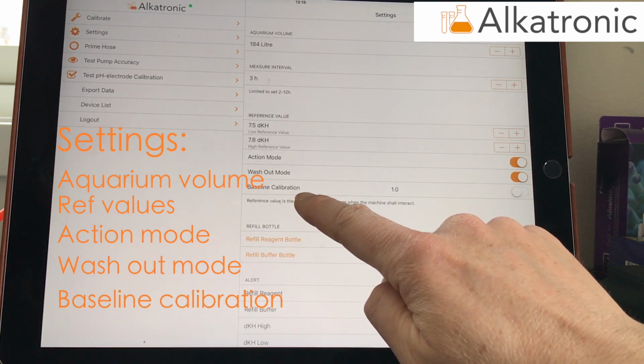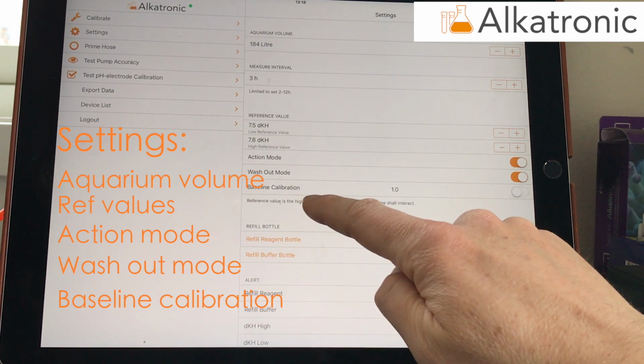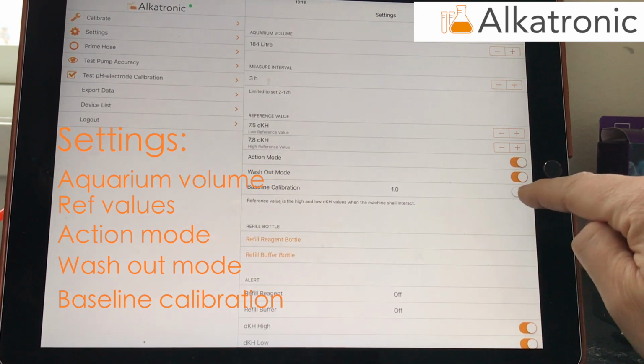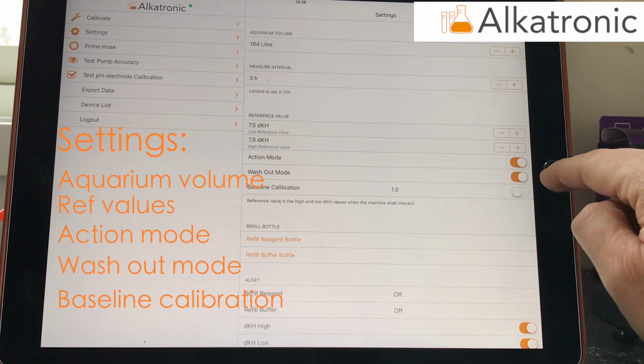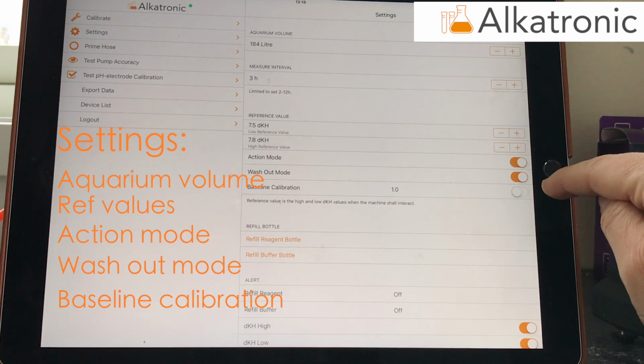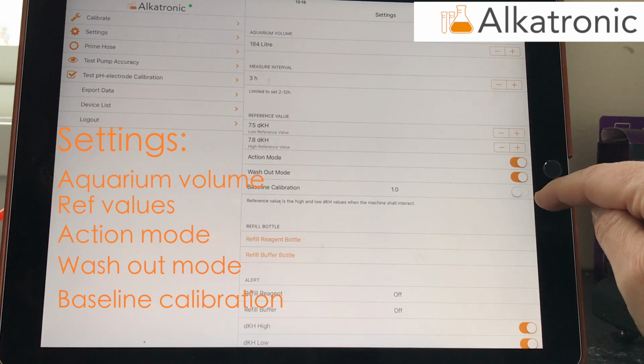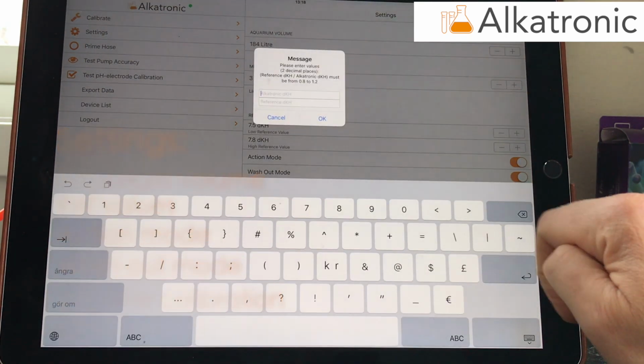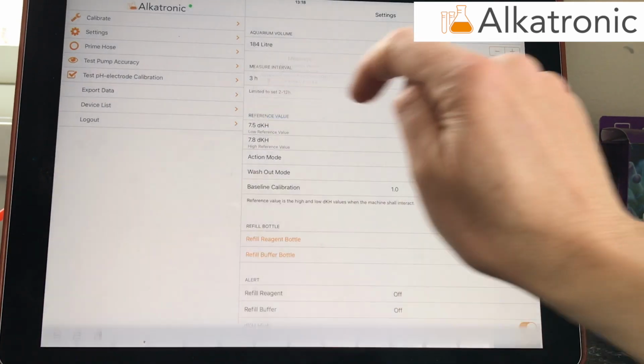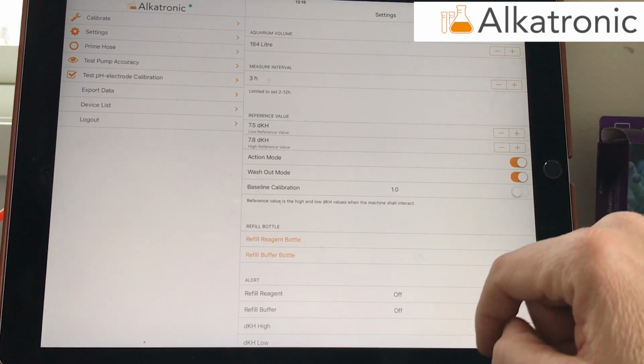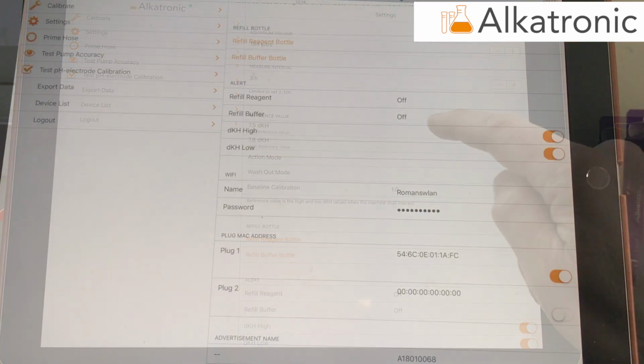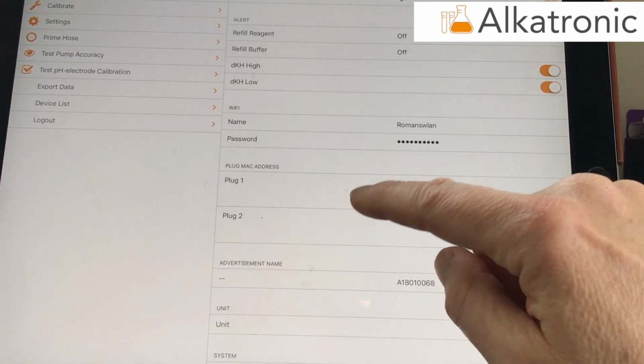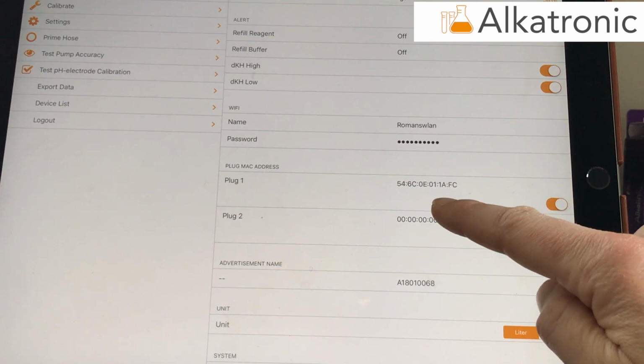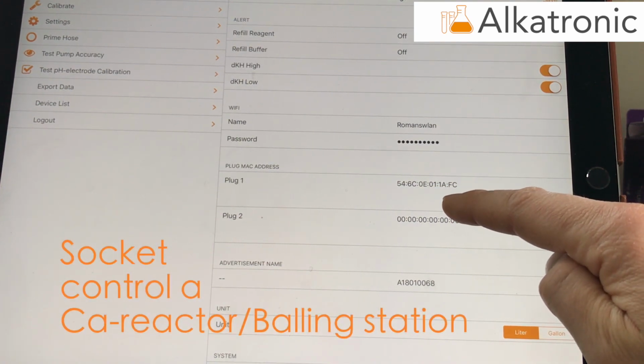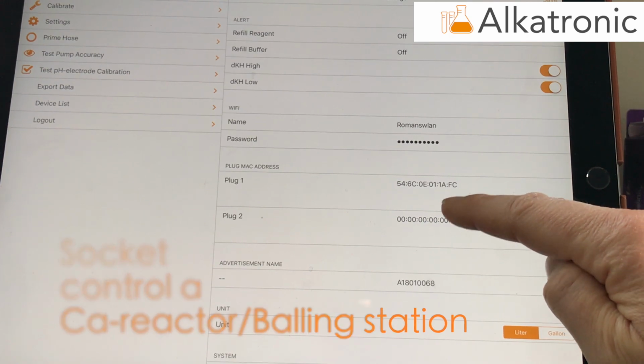Baseline calibration is a very nice new feature in the coming software update, very soon. It allows you to do some baseline calibration, correcting for any error in the reagent. As you mix the reagent yourself, there could always be some percent deviation from perfect mixing. The baseline calibration will allow you to adjust that and get perfectly accurate results, also with a not perfectly mixed reagent solution. Here you have the Wi-Fi settings, and here you have the intelligent socket plug. The socket plug is controlled by Alkatronic and can in turn control the calcium reactor or the balling station.